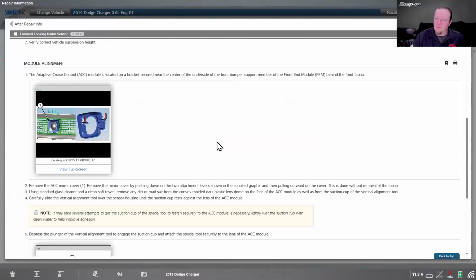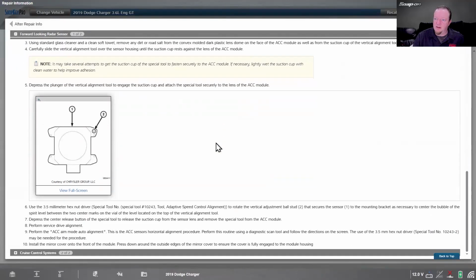So that's your alignment, and that's going to talk about how you have to adjust it. Rotate the vertical adjustment ball stud that secures the sensor to the mounting bracket as necessary to center the bubble of the spirit level between the two center marks on the vial of the level located on top of the vertical alignment tool.